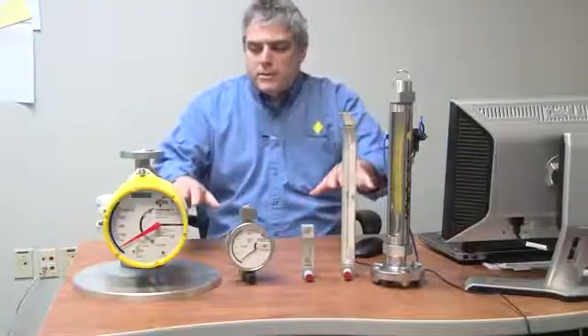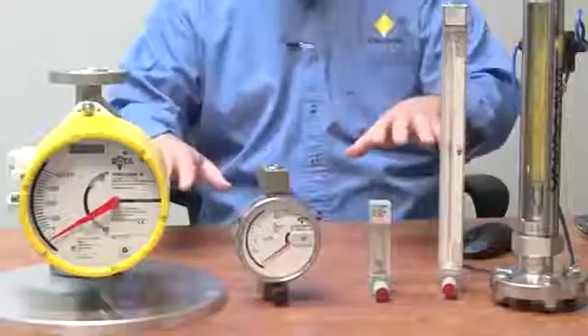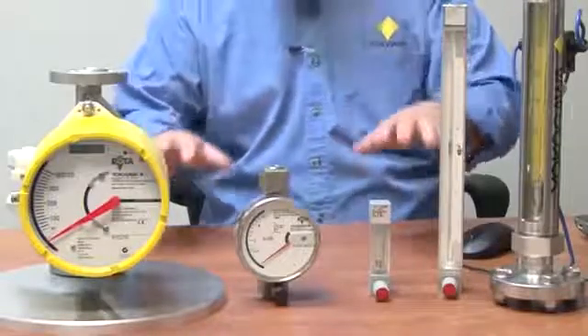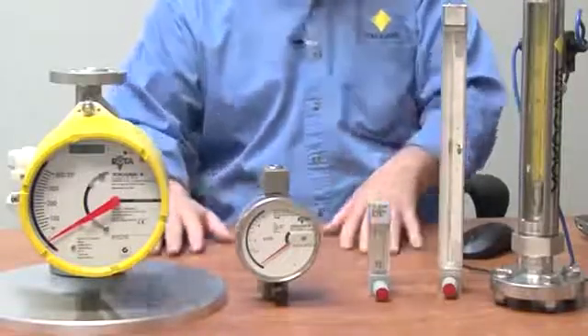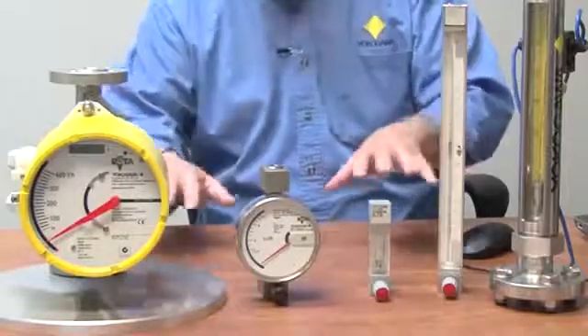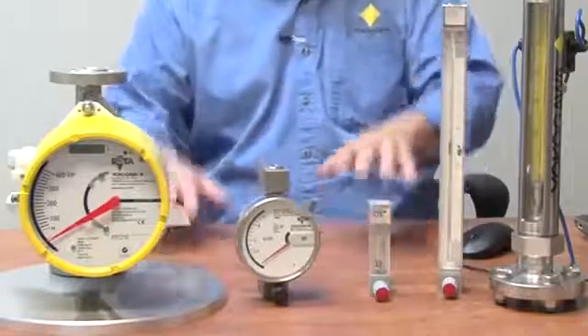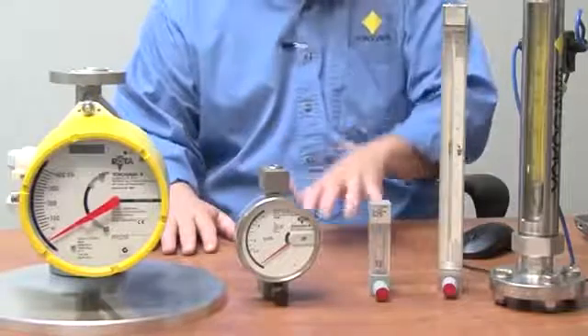All rotameters are direct acting measurement indication, require no external power supplies, are all suitable for gases and liquids, and they are precise measurements at a very low range.